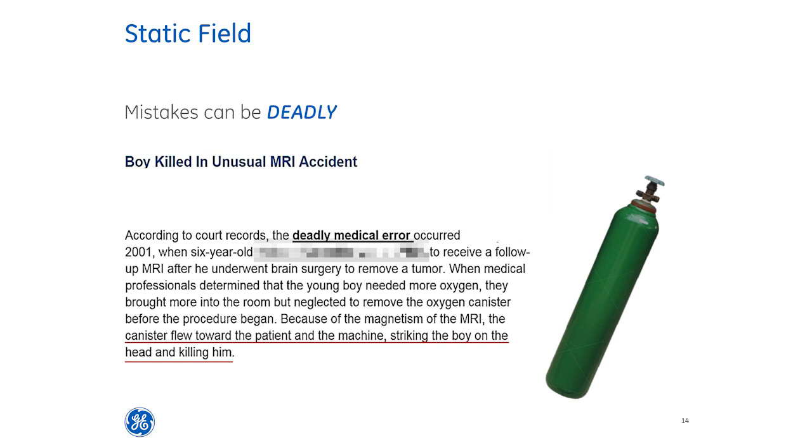This happened because someone took an oxygen tank into the scan area, not realizing that the one they held was not MR safe. The tank, attracted to the magnet, became ballistic and flew towards the center of the magnet, which happened to be where we scan, striking the child's head. Never take this lightly. Always respect the magnet and always assume that the magnet is active.